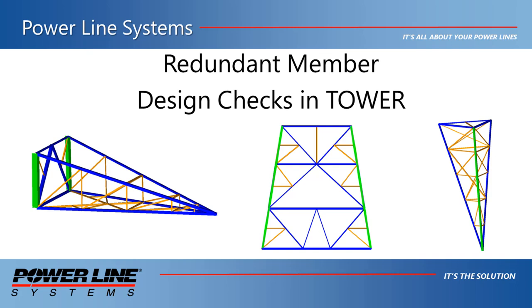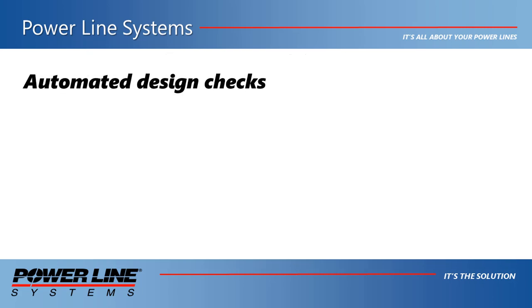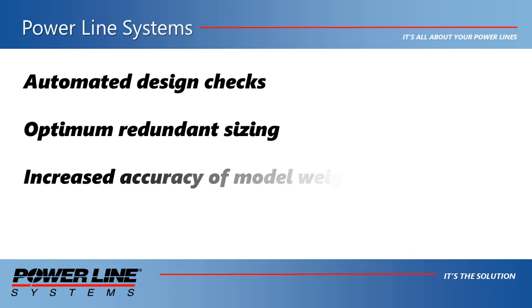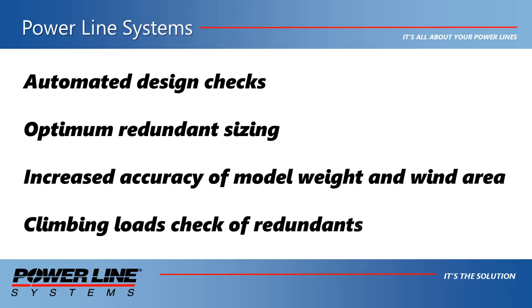It is not required to include redundant members in your tower models, but including redundants provides several advantages: it allows for automated design checks based on a selected design code; optimum sizing based on actual loads or as a percentage of the load in the braced member; a more accurate automated calculation of tower weight and wind area; and the ability to check redundant members for climbing loads from personnel standing at the middle of the member.